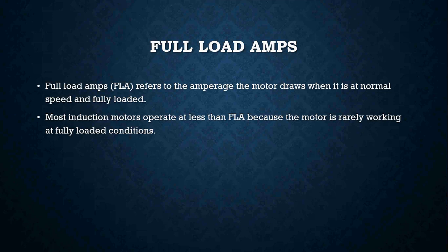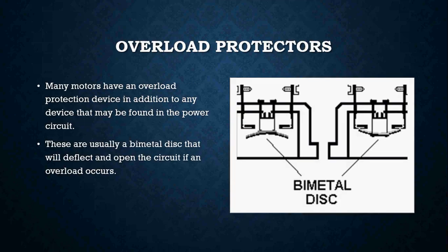It may fail maybe in another year or so. But just let people know that they do have a problem with the motor. If everything is within range or operating below what the motor is rated for, then I would probably say that the motor is still in relatively good condition and you probably shouldn't have much of a problem with it.